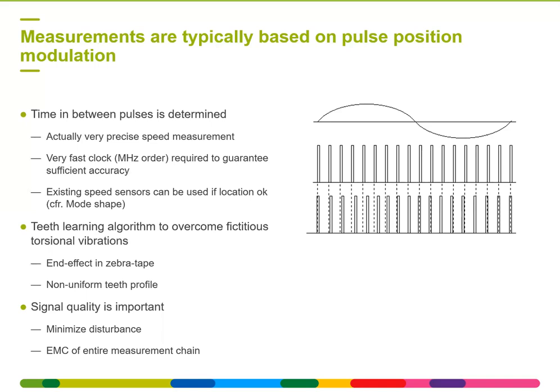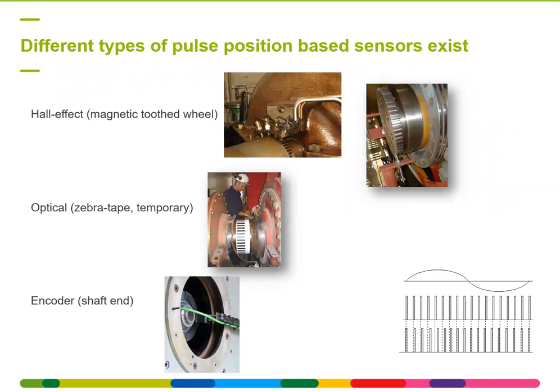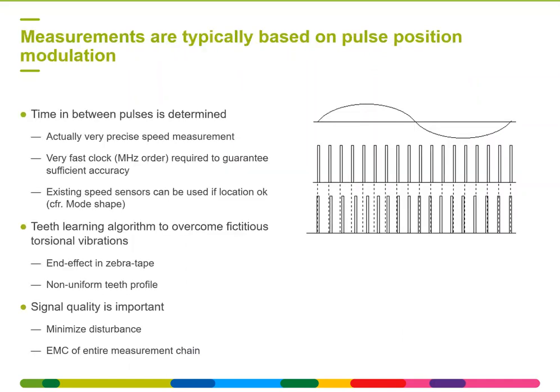Typically, fictitious torsional vibrations are overcome by learning what the geometry of the toothed wheel is. So this is, for instance, included in the software. But if you do not do this, you could have components at one times and harmonics of the rotational speed. Of course, a toothed wheel is not perfect by manufacturing. There's always slight differences between the different teeth. If you connect a zebra tape, for instance, onto the shaft, which is a tape where you have white and black marks, as you can see on the second figure here, for the optical probes there, typically you have an end effect where you have one larger black or white pulse. So there again, you need to overcome this in the software.